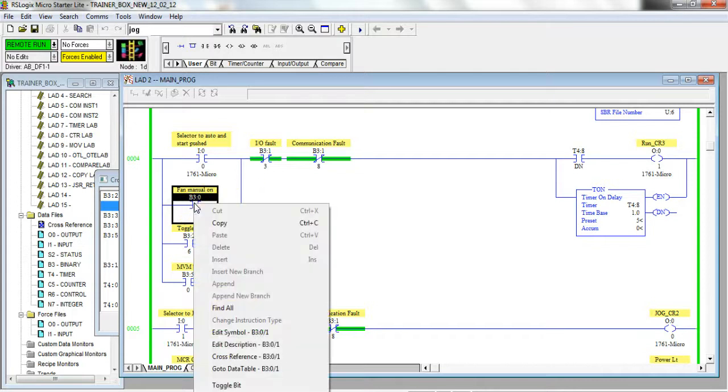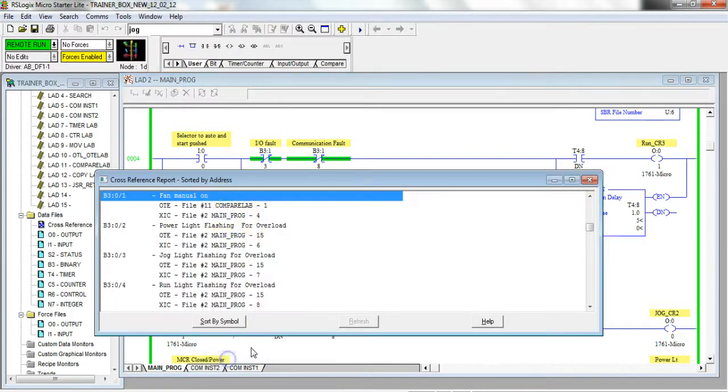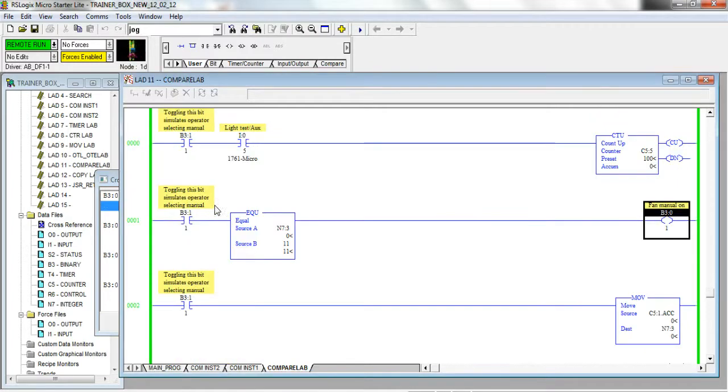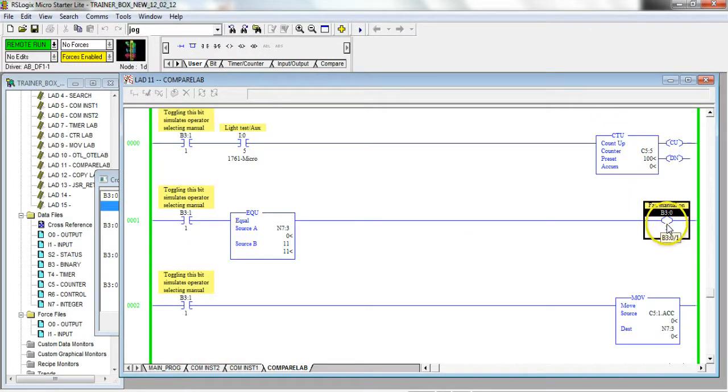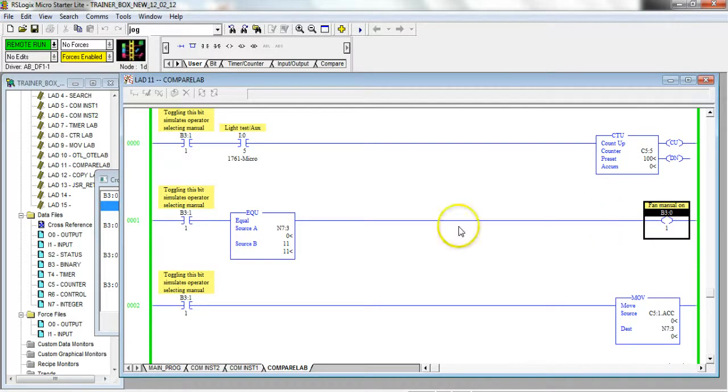In this case I'm going to do a right-click cross reference. You'll see there's an OTE or a coil that is essentially forcing that toggle bit off, so it's not allowing me to toggle it.